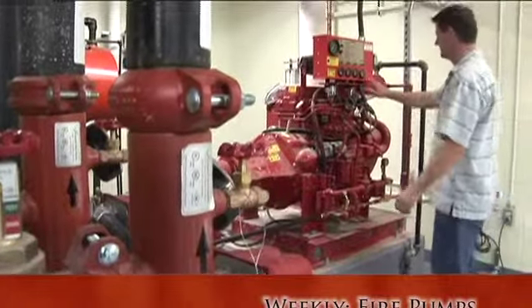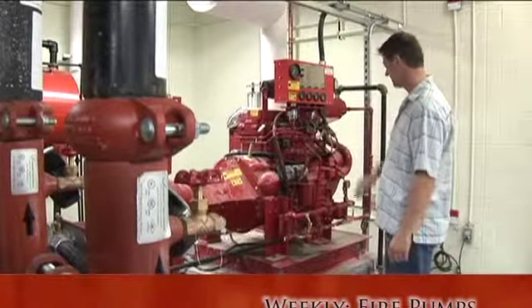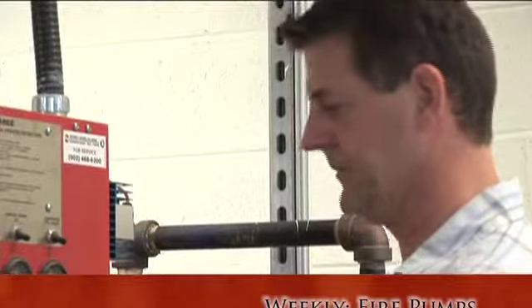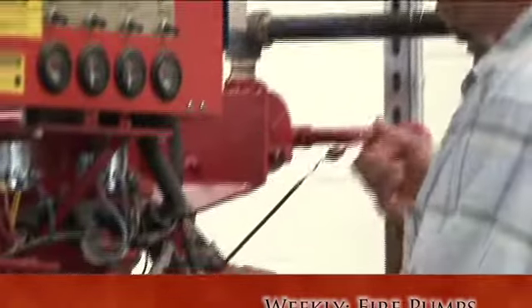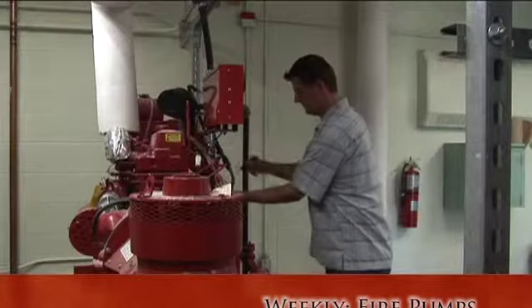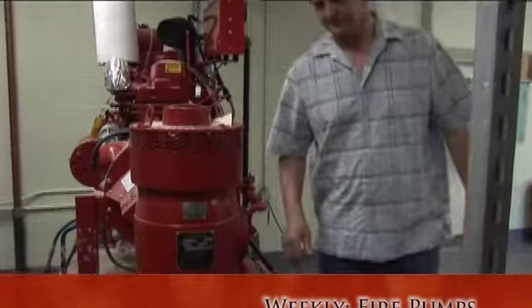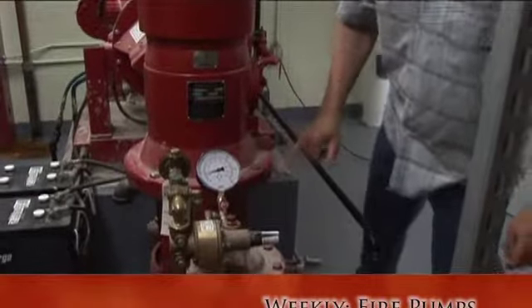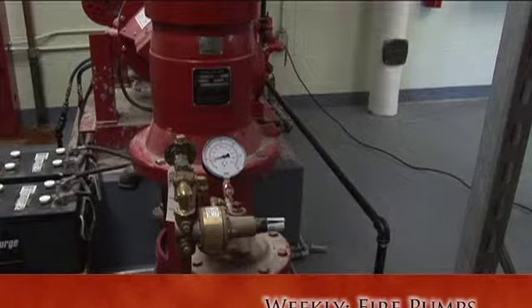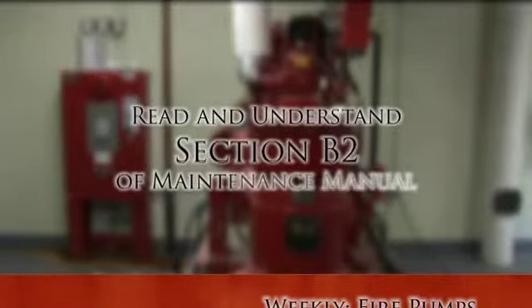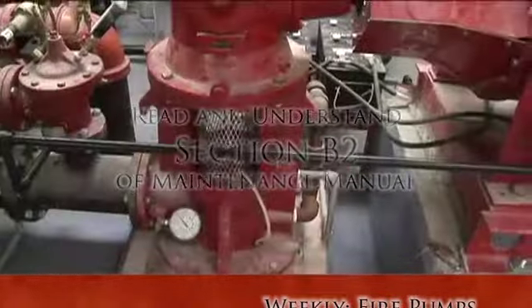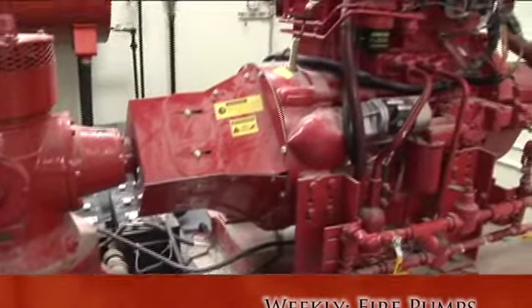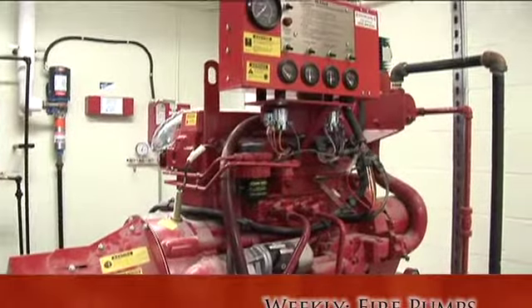Fire pumps can be either electric or diesel. Each has its own weekly checklist and must be inspected and tested thoroughly. Both types of pumps must be run weekly for 30 minutes to ensure their correct operation. All fire pump systems must be inspected and tested to confirm that the pump system is in good condition. This includes valves, piping, gauges, and suction screens. The pump's electrical system also needs to be inspected and tested. You must read and understand Section B2 of your maintenance manual for specific weekly tests and inspections. Now, if a problem is discovered, contact your supervisor immediately to have certified technical personnel service the fire pump.